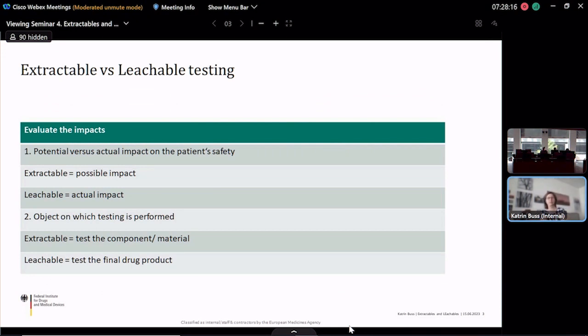So the difference is the potential impact on patient safety. And the impact needs to be evaluated. So an extractable has a possible impact because it's not for sure that it will occur as a leachable, but the leachables are those substances which actually may have an impact on the patient's safety or on the quality of the product, and by this on the patient safety. And the testing for extractables aims to test the component or the material for a component selection. It's during the development process, and leachable testing is done in the final drug product. Next slide, please.